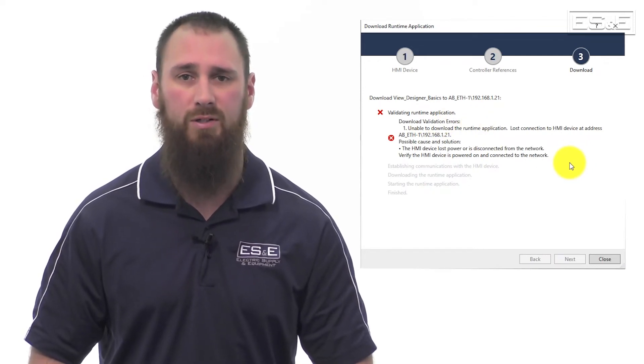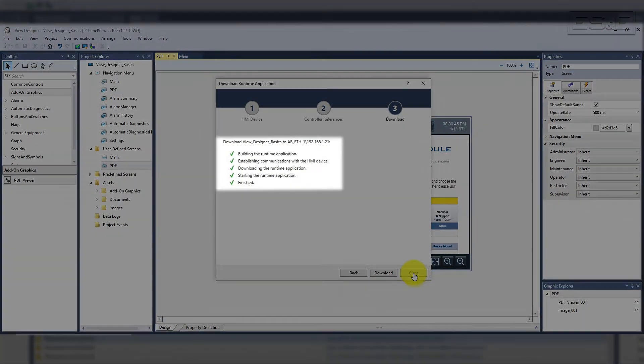If your software and firmware do not match, the download will fail and prompt you that the project revision does not match the revision of the panel view. Once the download completes, you will see green check marks and it will say complete.